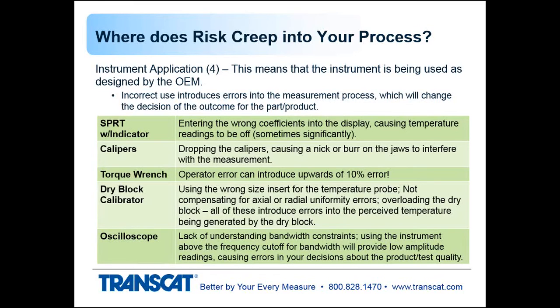SPRT with an indicator: entering the wrong coefficients into the display will cause temperature readings to be off, and sometimes that can be very significant. There are ways to prevent that now, like using Infocon connectors that automatically transfer the coefficients into the readout. But if you don't have those, that's something to be careful of. If you get the wrong coefficients assigned, or if you have the old coefficients assigned to the newly calibrated probe, you're going to get incorrect temperature values.